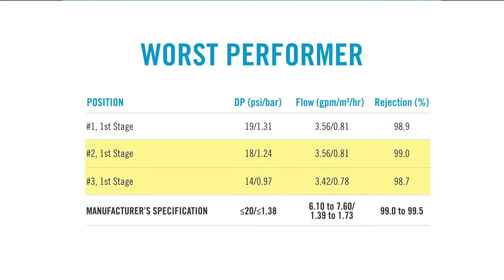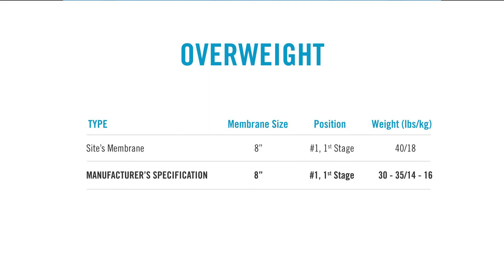We reserve positions number two and three for full element cleaning, so we can take the solutions we find in the lab, apply them on a large scale, to further prove their effectiveness. The first thing we do with our chosen element is check the weight on it. We found that it weighed 40 pounds, while new elements typically weigh 30 to 35 pounds. That's five extra pounds of mass inside of this element, blocking the channels and making it harder for water to pass through. We associate high weights like this with elevated delta pressures, which we saw during the single element wet test. This is our first piece of evidence that we're on the right track.